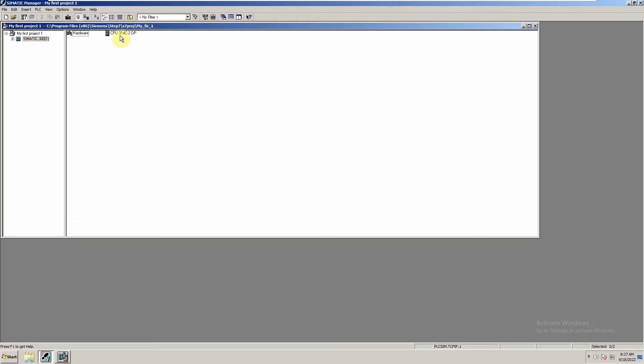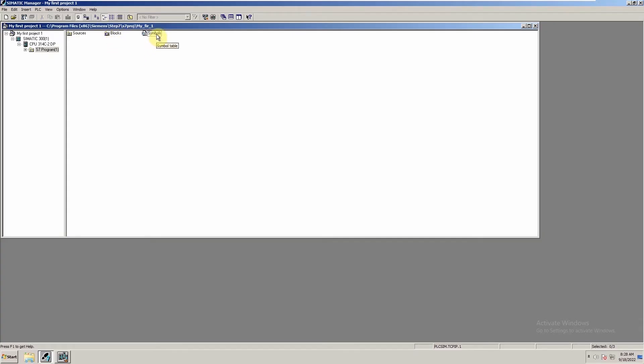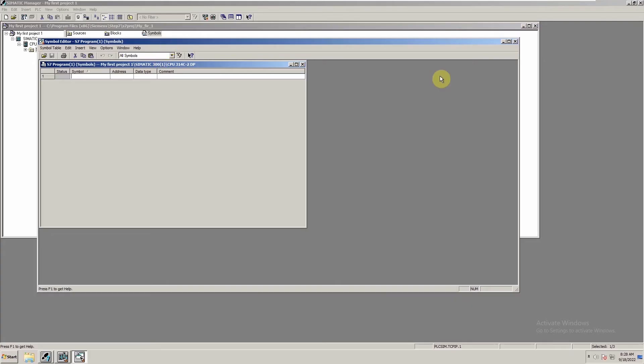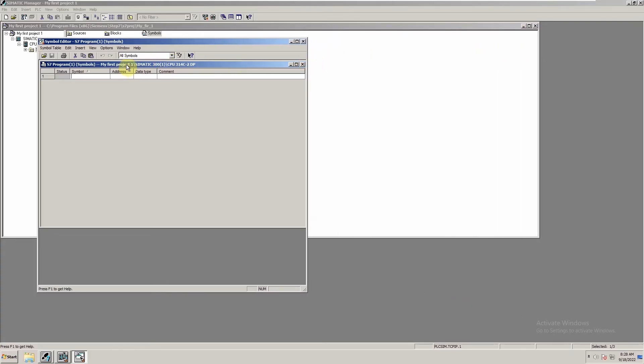Now we will save and compile the hardware configuration. It has saved and compiled without any errors. We will minimize the hardware configuration and go back to our project. You can see that CPU 314C has now been included in the project. We'll open this CPU, go to S7 Program, and you can see here Sources, Blocks, and Symbols. All of our programming will be done inside the Blocks, and the memory bits we create can also be stored in the Symbol table.